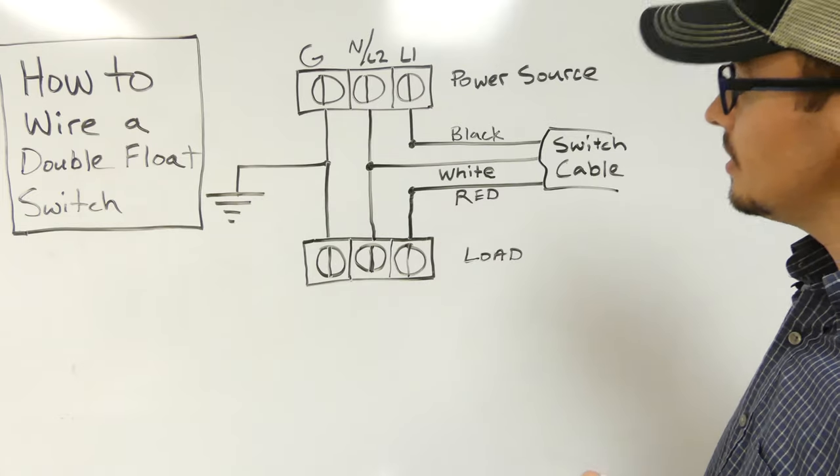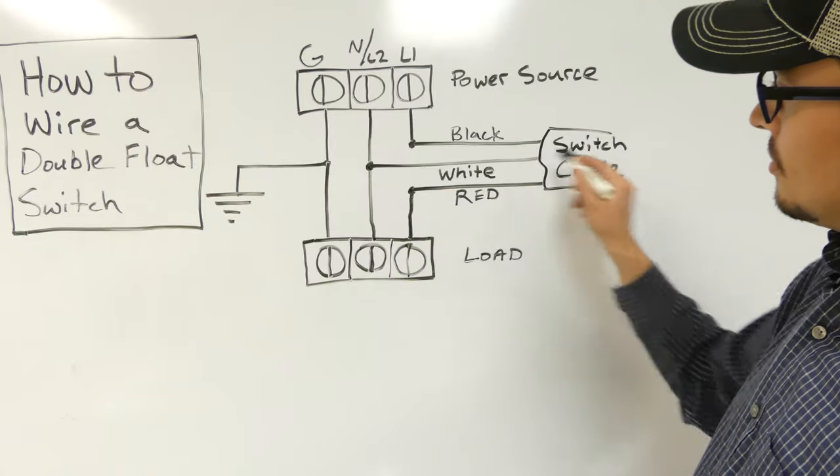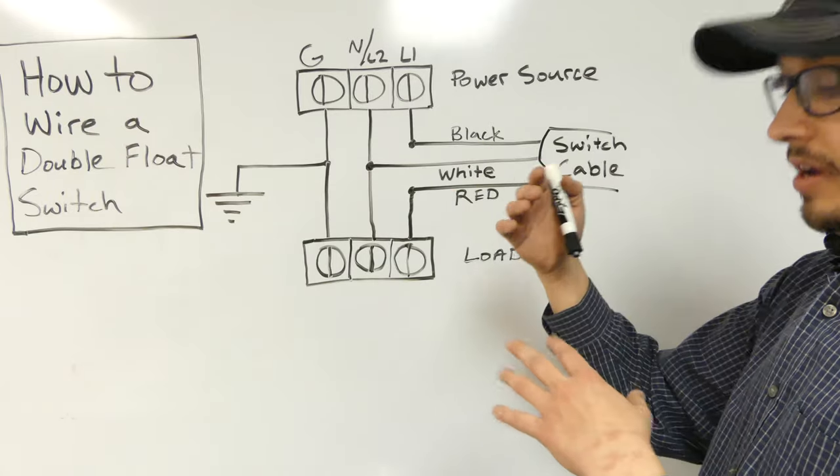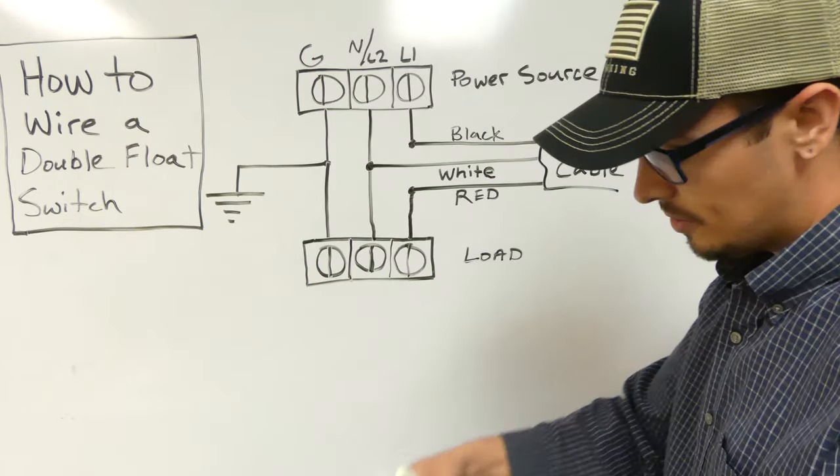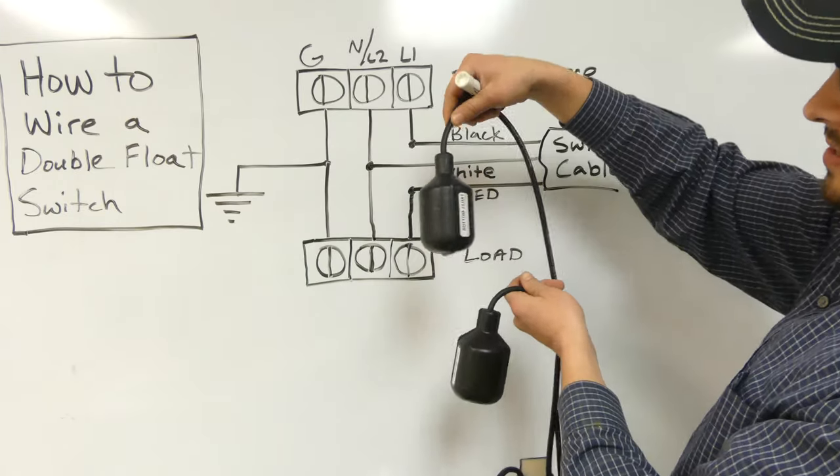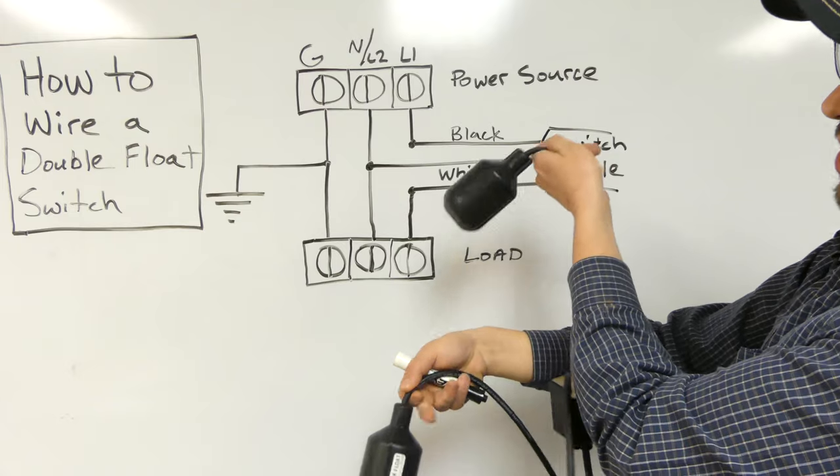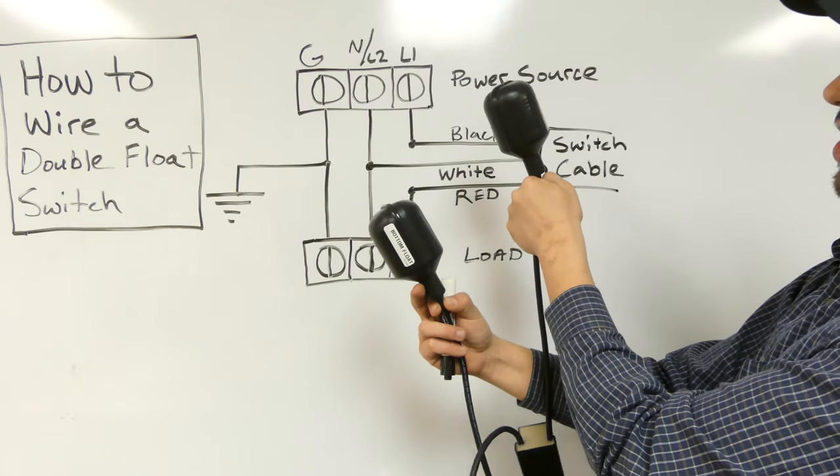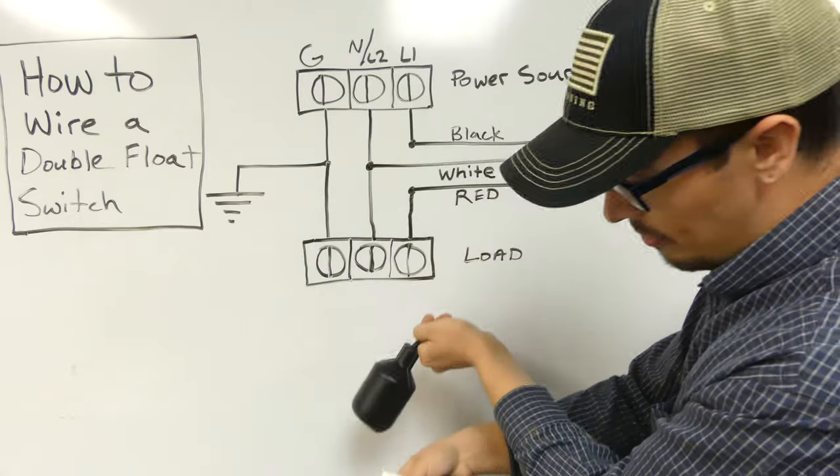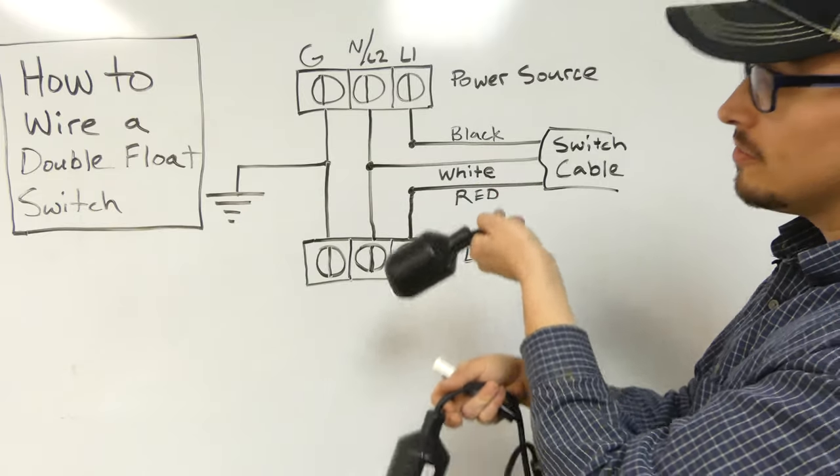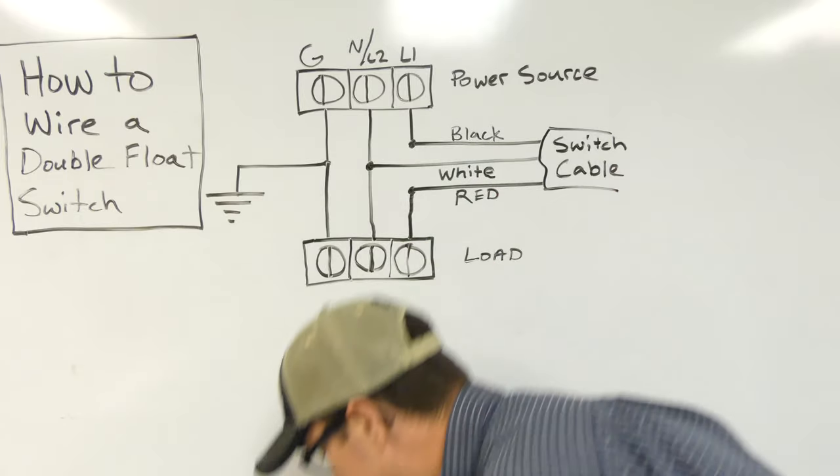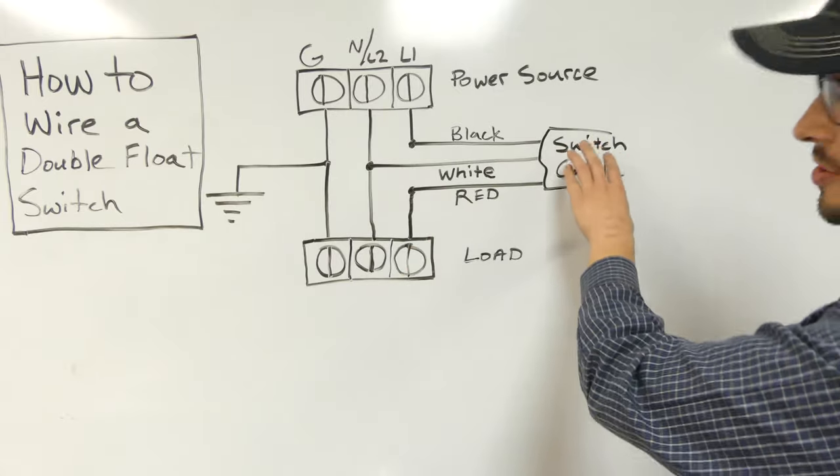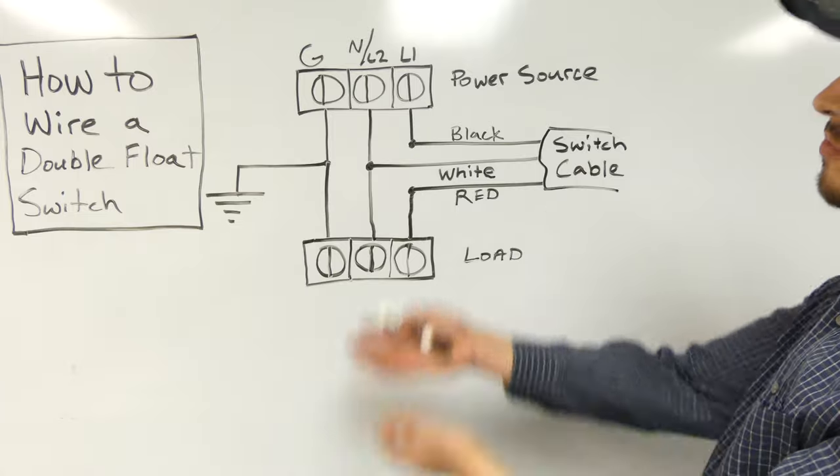So essentially, what we're doing here is with that holding circuit that's created with the relay, we're able to have, let me grab the floats again. So the simple way that this operates, I got them backwards, but it requires both floats to be in the up position for the system to turn on and then both floats to be in the down position for the system to turn off.